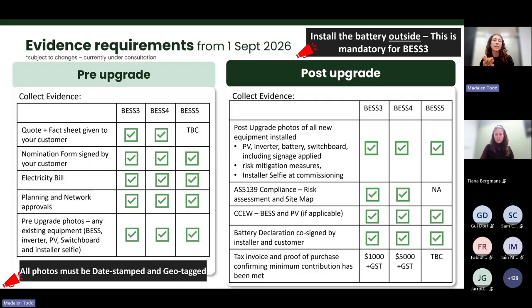For BESS 5, this isn't required, as AS5139 requirements don't apply to batteries over 200 kilowatt hours according to the standards. So it's just the wiring standards in BESS 5 that you have to comply with. And obviously for all of BESS 3, 4, and 5, you also have to comply with the manufacturing guidelines of the specific product you're installing.